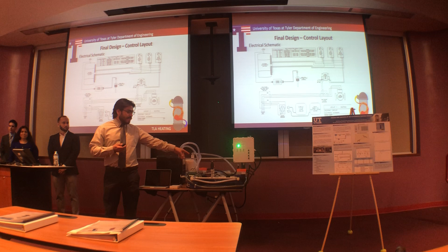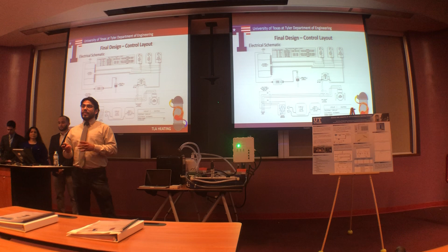Some of these auxiliary systems include a 24 volt AC transformer that powers our three actuators, as well as an AC to DC converter used for the flow meter, and we also have a pump that's powered by those 120 volts.